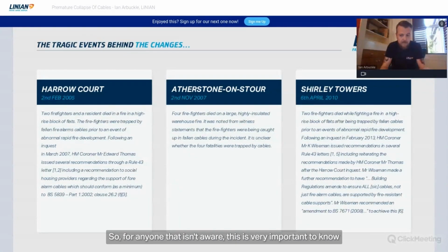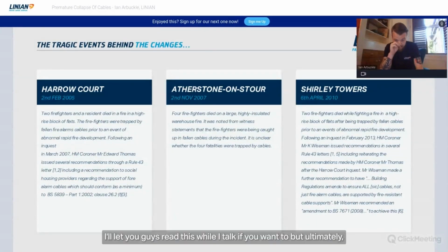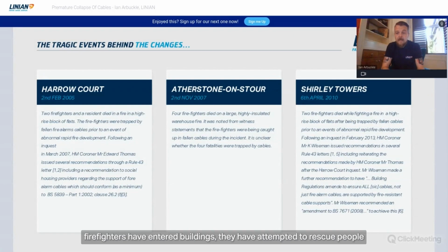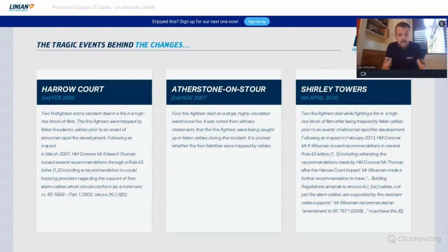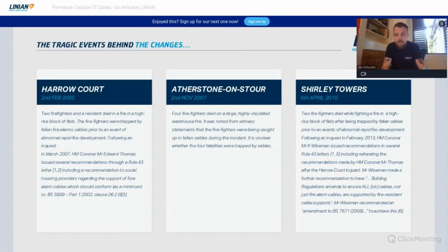For anyone who isn't aware, this is very important to know when you're assessing installations for premature collapse, because this is why we have the regulation. Tragedies have taken place. I'll let you guys read this while I talk, but ultimately firefighters have entered buildings, attempted to rescue people and become entangled in collapsed electrical cabling. That has resulted in the death of them and the people they were trying to rescue. And it is entirely preventable at the installation stage.